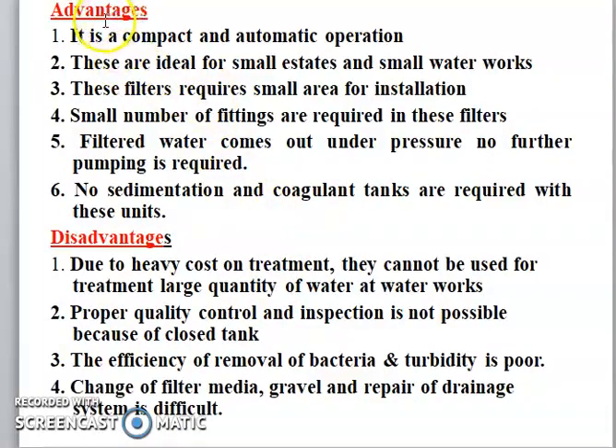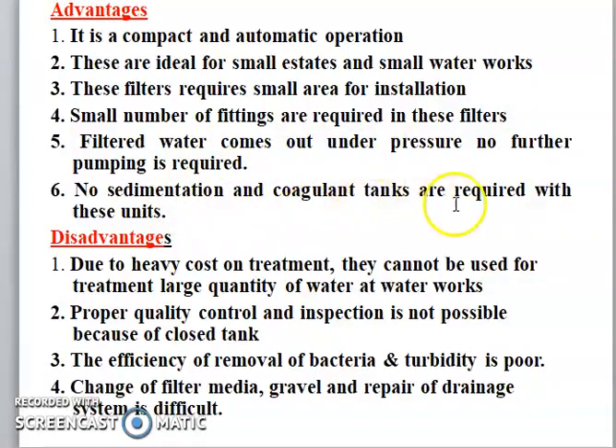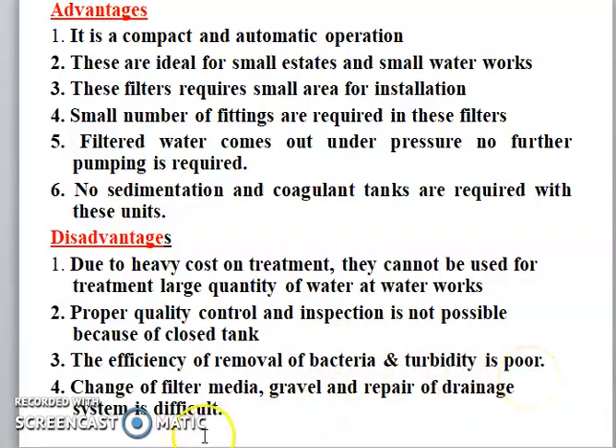Advantages of the pressure filter: it is compact and automatic in operation; ideal for small water works; requires small area for installation; small number of filter units required; filtered water comes out under pressure so no further pumping is required; no sedimentation or coagulation tanks required for each unit. Disadvantages: due to high cost of treatment, they cannot be used for large quantities of water; proper quality control and inspection is not possible because of the closed tank; efficiency of removal of bacteria and turbidity is poor; repair of the drainage system is difficult.